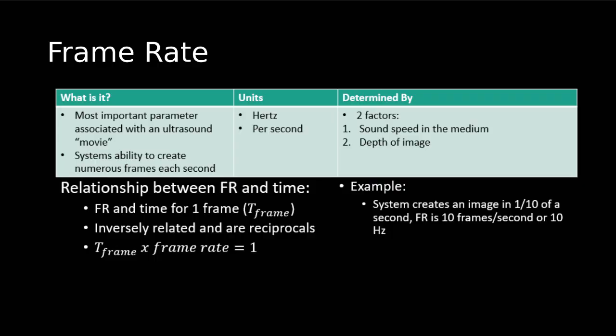Frame rate is the most important concept for our system's ability to image certain structures seamlessly — how seamless can we make that movie? It's our system's ability to create numerous frames per second, measured in hertz. It's determined by the depth of our image and the speed of sound in the medium. We can affect some components of our frame rate, but the speed of sound in the medium we can't really control. So we can manipulate frame rate a little, but it is ultimately also determined by the speed of sound in that particular tissue.